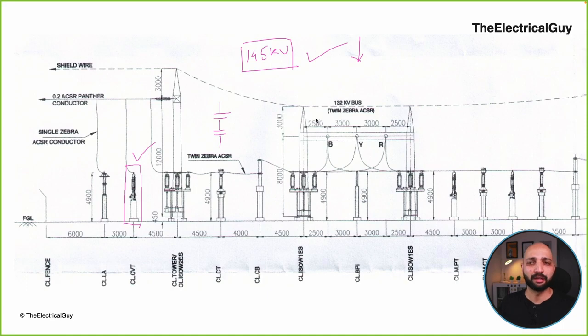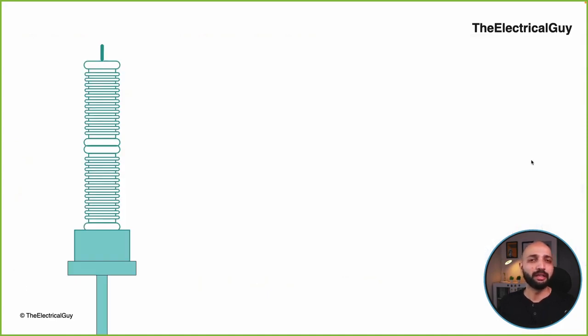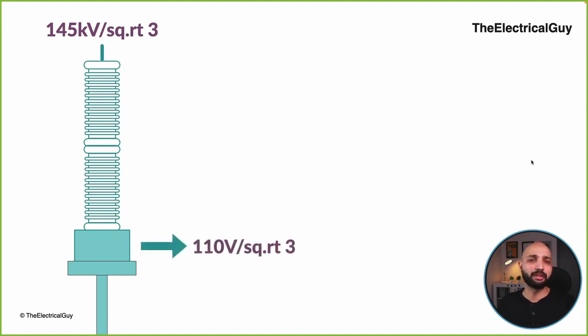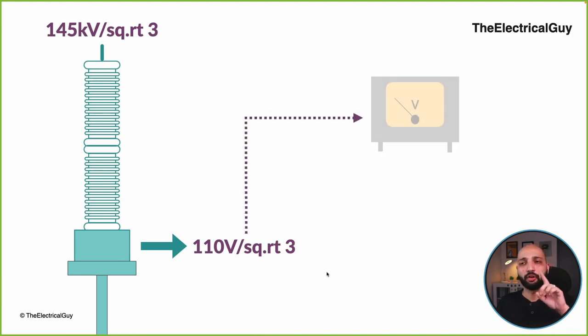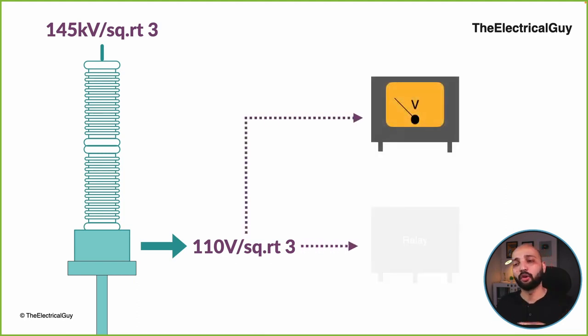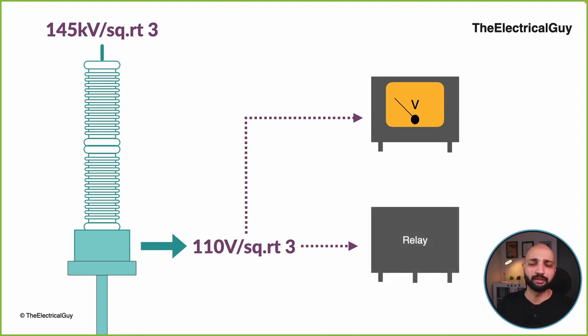Now what it does is, let us have a look at that. So basically, the CVT accepts the high voltage at the primary terminal, let's say 145 kV by root 3 because it's a single phase unit. And then at the output, it gives a much lower voltage, let's say 110 volt by square root of 3 or 220 by square root of 3. And then this input can be used either for metering or for relay, or both simultaneously. It is also possible. And for that purpose, capacitive voltage transformer or CVT is used.